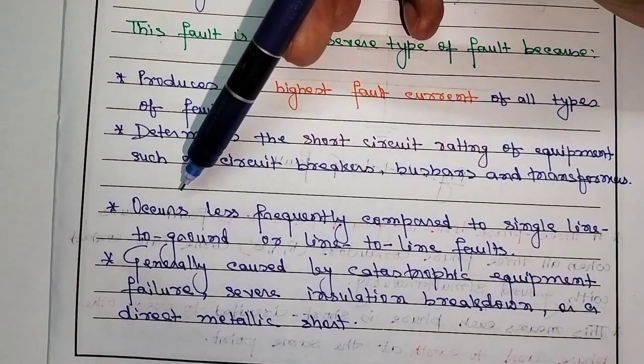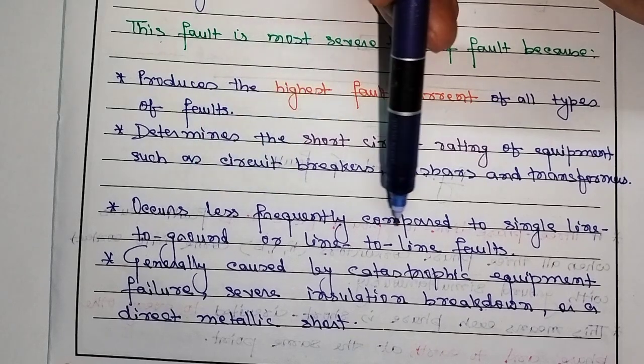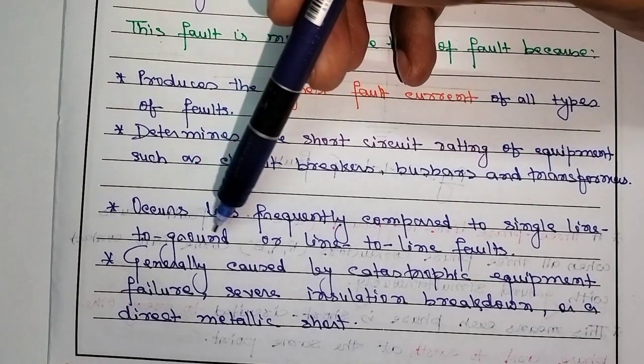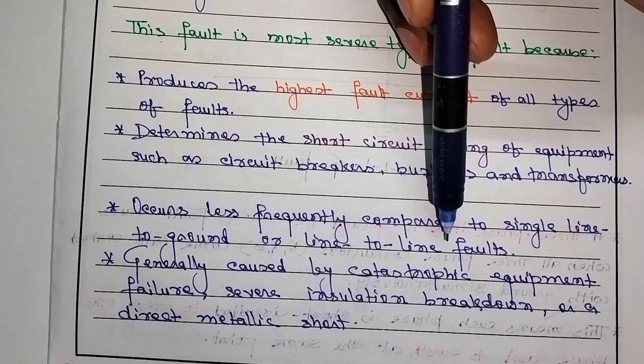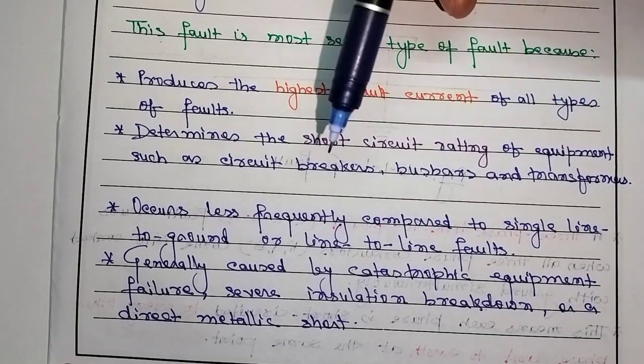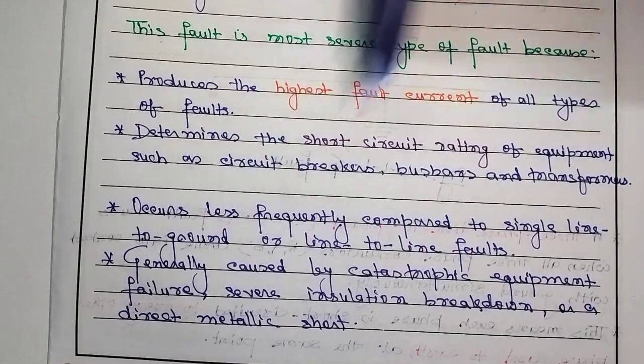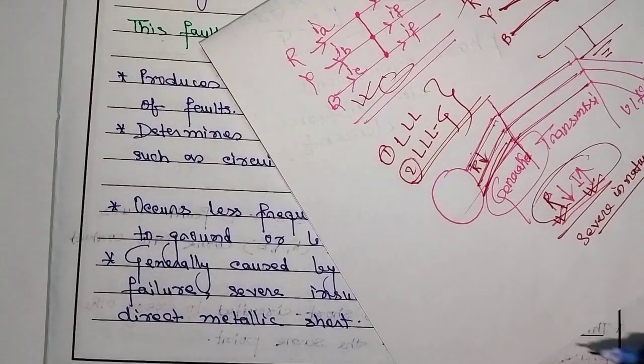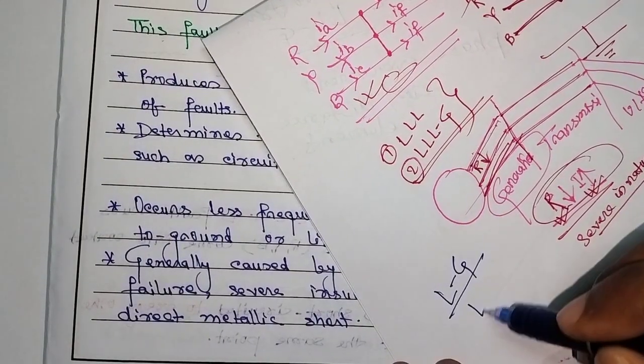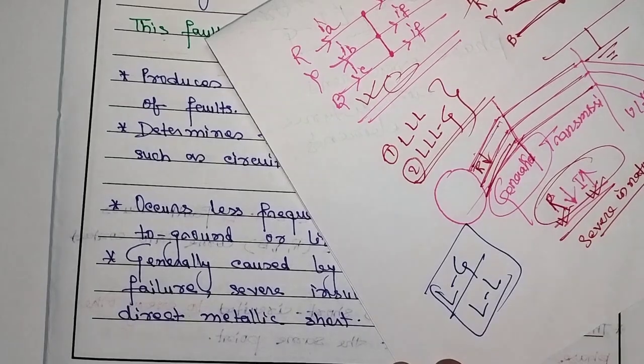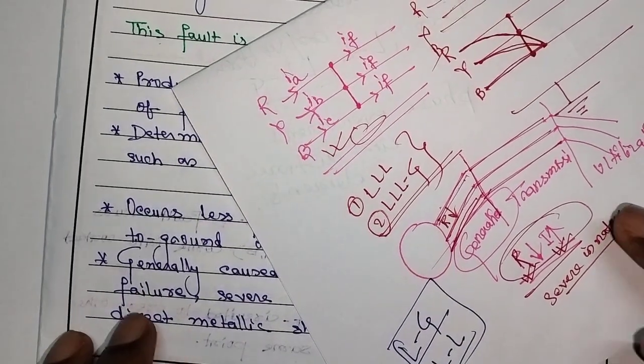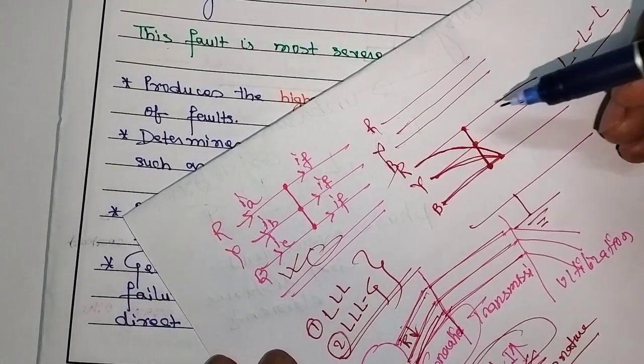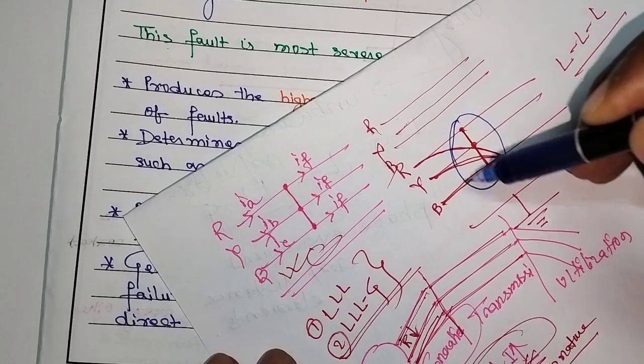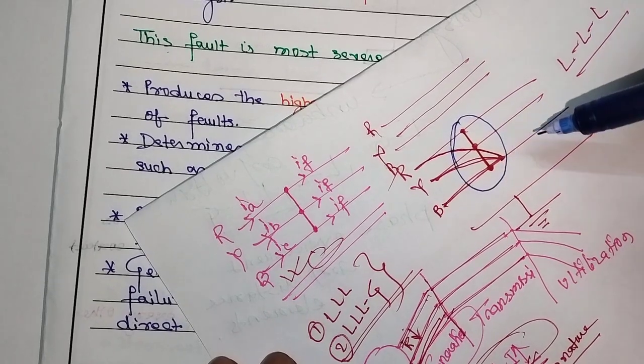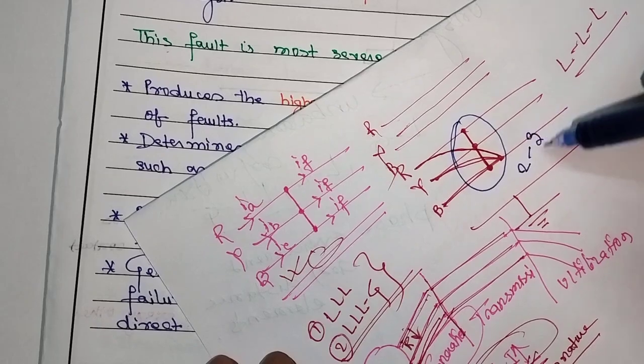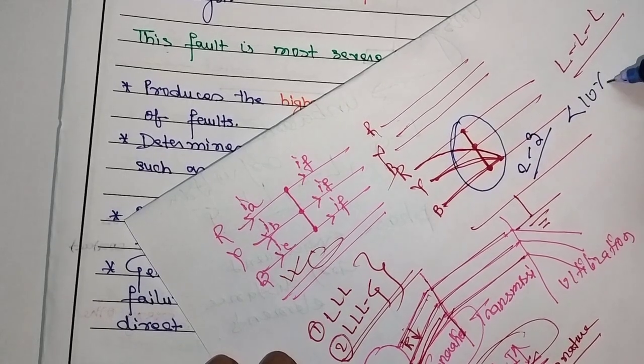Next, it occurs less frequently compared to a single line to ground or line to line fault. If you compare with the other types of faults, like the single line to ground fault or the line to line fault, it occurs very rarely, when all three of the system conductors get connected and this type of fault occurs. Very rare, maybe 2 to 3%, less than 10% of faults.